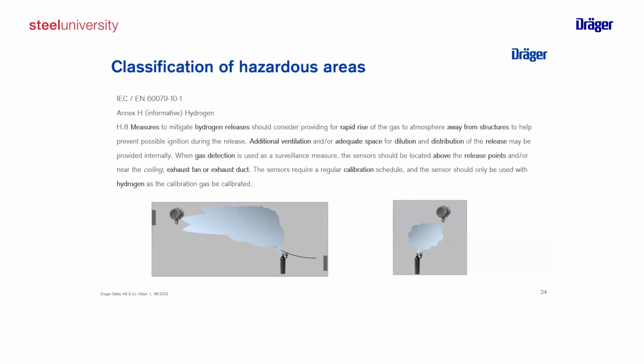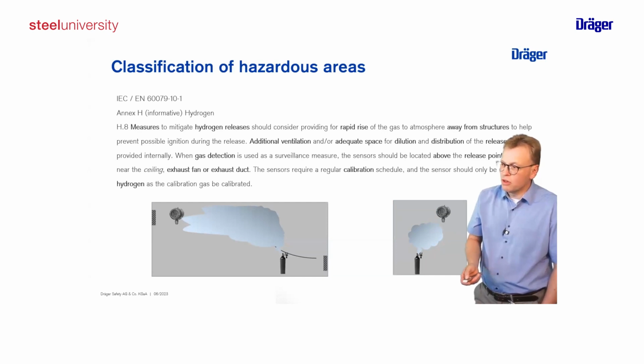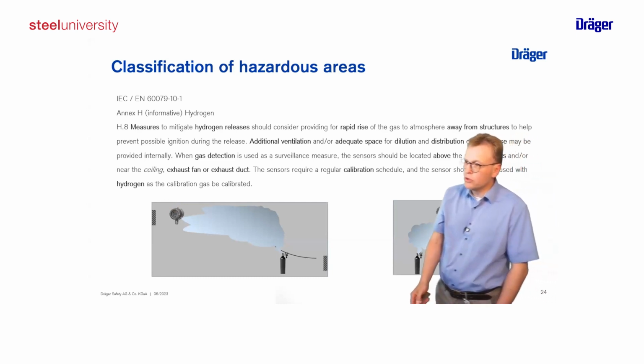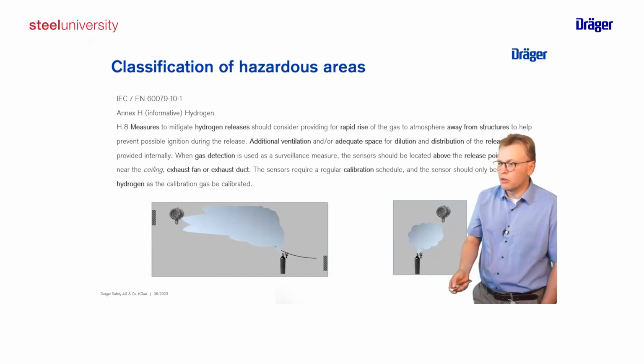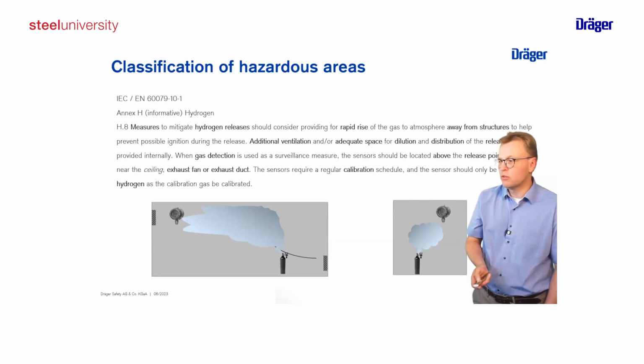And this leads then to point 8 in this appendix about the positioning, as mentioned before. Depending on whether we have just a normal room where we have a leakage, the gas will go up and we should position a detector close to or higher than the expected point of release. When we have ventilation in between, then the detection should be very close to the area where we have the exhaust or the release point to the outside, because there's the highest airstream. So the probability is highest here that the detector can pick up the gas. For gas detection, it's always important, especially with this kind of technology, that the gas needs to reach the detector. If by the ventilation the gas molecules are moving a different way, the detector has no chance to pick up the concentration, or the concentration indicated could be very low and not represent the actual situation.